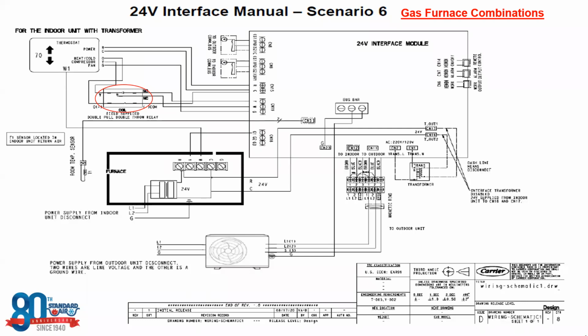But in essence, to make this work, we need that field supplied relay to be able to differentiate between a W1 call and a Y1 call. Okay, but again, we're using the O terminal to feed out instead of the W1 to the 24 volt interface. And again, that is a field supplied relay. Okay, and now your W1 from the thermostat, when it's set up as a dual fuel operation, is going to be the output to turn on your gas furnace, just like any traditional system would be.